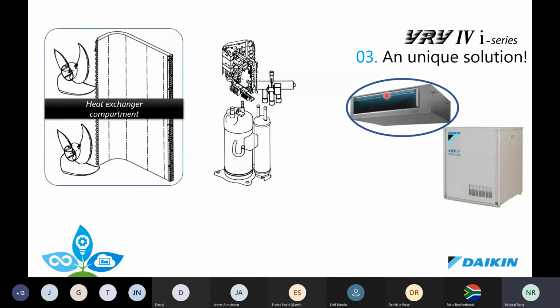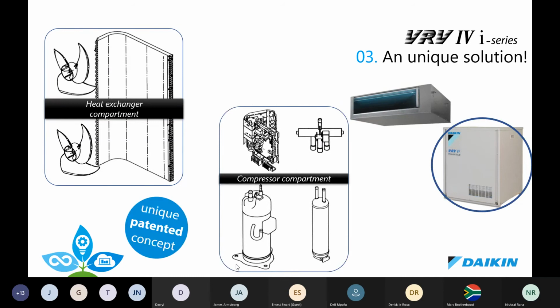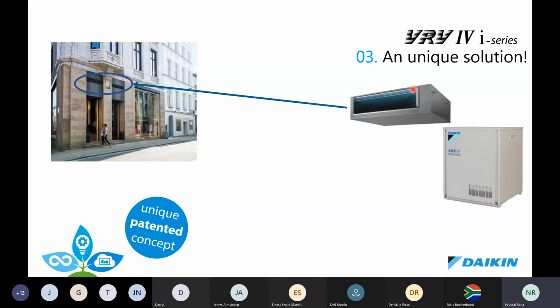So basically your components, what we've done is this becomes now the outdoor fan module, which would normally have discharged on the side. We've shrunk it and made it the same size as an indoor unit. And we've taken the compression module itself and made it the size of a dishwasher. The indoor-looking unit that was shrunk is normally the air discharge point, the air side of the condenser unit system. We've shrunk it so that it has an inlet and an outlet. So you have warm air blowing out, that would be here or here, and cold air coming in. And basically you've got no condensers at all on the system.